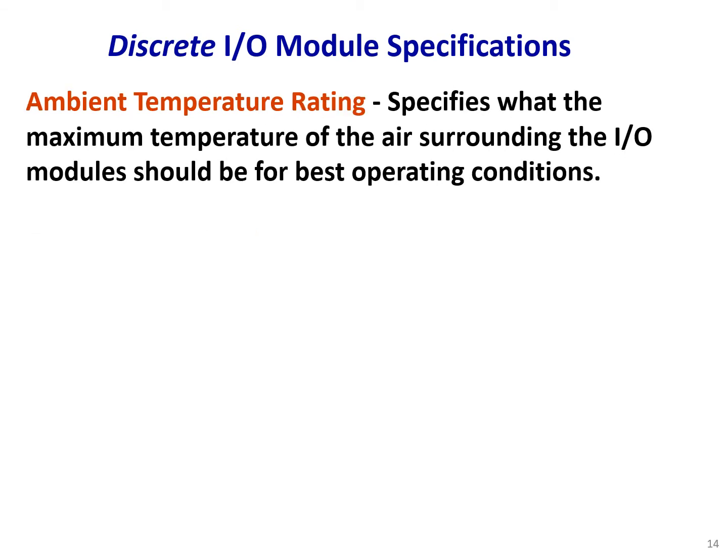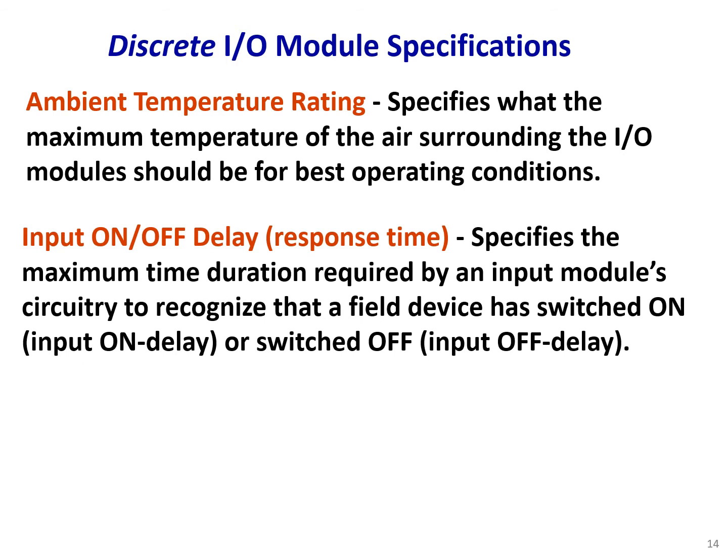Ambient temperature rating specifies the maximum temperature of the air surrounding the I/O module for best operating conditions. Input on/off delay response time specifies the maximum time duration required by an input module's circuitry to recognize that the field device has switched on or off. The input device should be on for a certain period of time, and there is always a delay — what is the response time of the module?